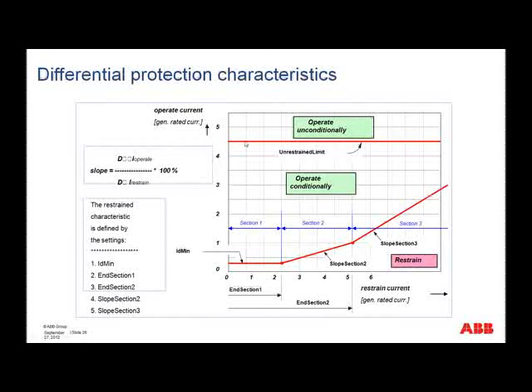So this is then showing that. So here you see we have the unrestrained or high set threshold. Here we have the characteristic. It's in 3 sections. The ID min or minimum sensitivity here can generally be set for somewhere around about 10 to 20%. First slope starting here at about 100 to 125%, and second slope here at about 300%. Okay, and then the slopes for the first slope here around about 40%, and for the second slope around about 80%. And these values have shown to be good values for the differential function.